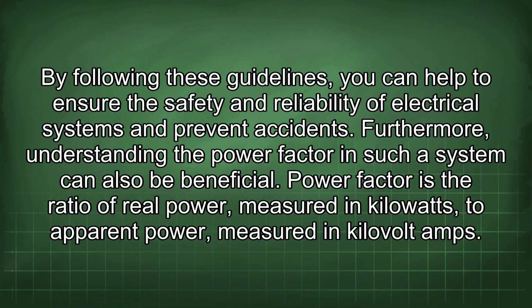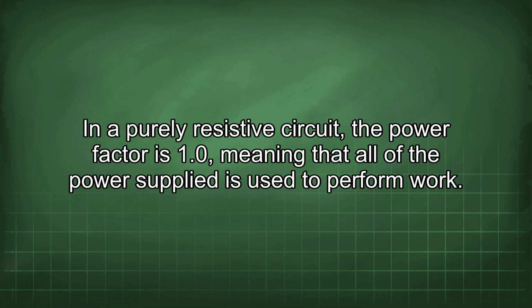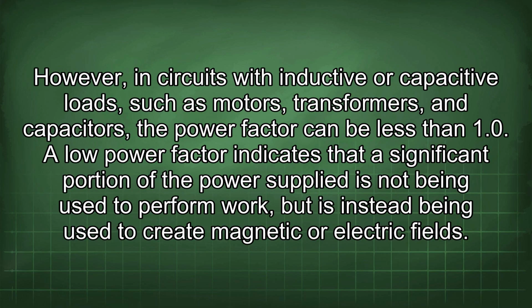Furthermore, understanding the power factor in such a system can also be beneficial. Power factor is the ratio of real power, measured in kilowatts, to apparent power, measured in kilovolt amps. In a purely resistive circuit, the power factor is 1.0, meaning that all of the power supplied is used to perform work.